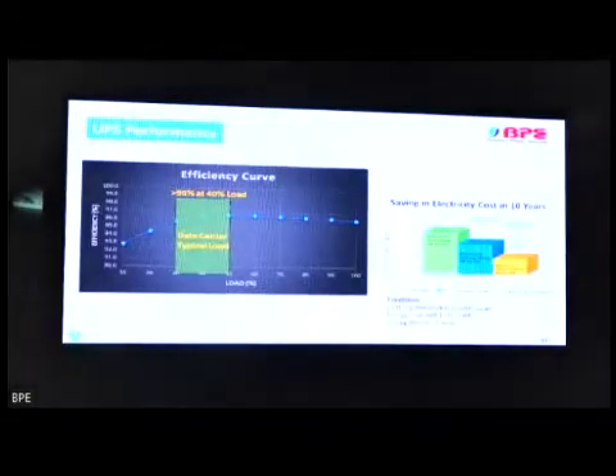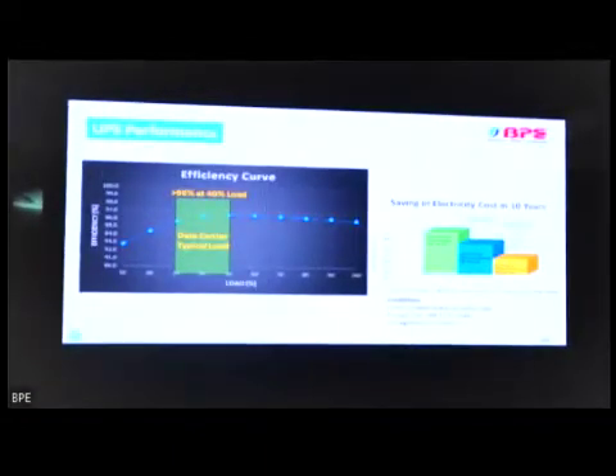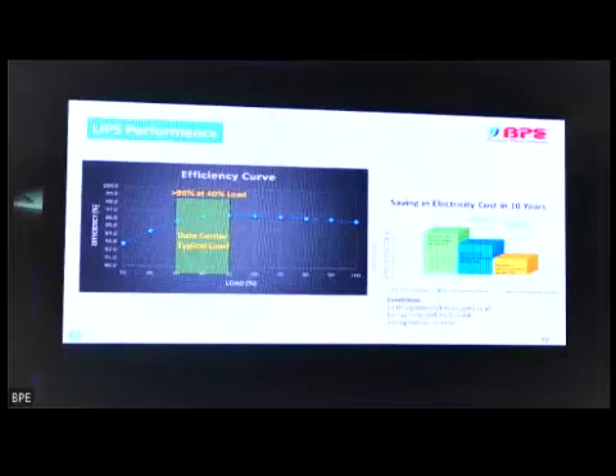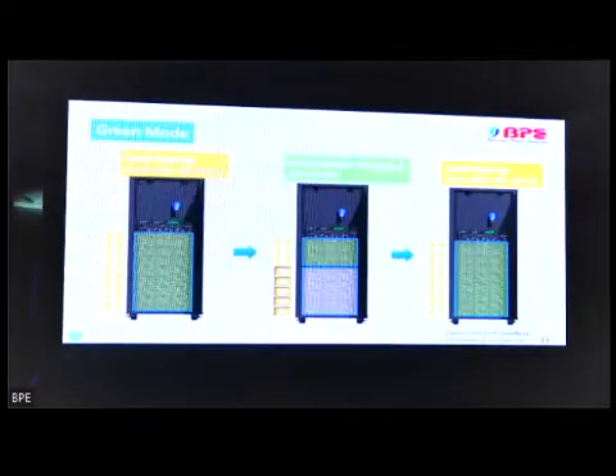Even if one fan fails, the module will still work with 70% of the load. So internal redundancy is also there. It can save up to 16,384 event logs, which is again industry highest. And here is the power module. This is the flow of air. It's very lightweight, only 30 kg per power module, 3U height. This is the efficiency curve of this UPS. You can see that efficiency is even greater than 95%, even at 25% load, which is a very light load. So you can save this much electricity cost using this UPS in 10 years.